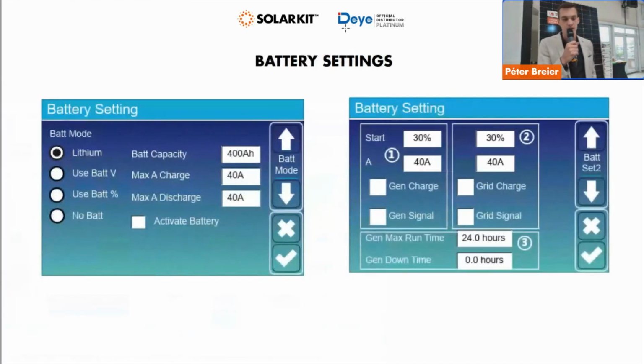Other than that, battery setting. Of course, if you are not using batteries, then please choose the no bat mode. If you are using Deye's own batteries or any compatible batteries, use lithium mode. And if you are using lead acid batteries, then you need to use BAT-V mode. Other than that, you can give the capacity of the batteries that you know from the data sheet of the battery. Also, you have to set the maximum ampere charge and discharge values. This is limited by the inverter and also limited from the battery side.